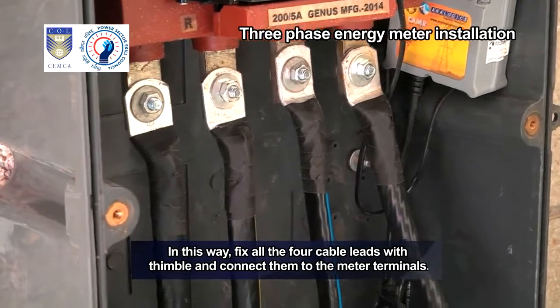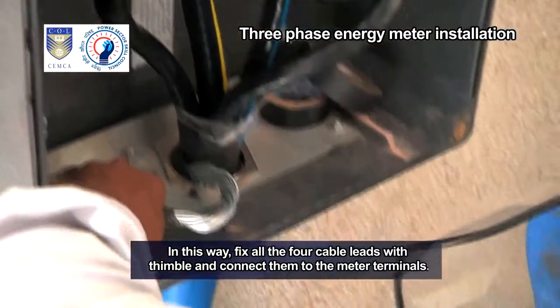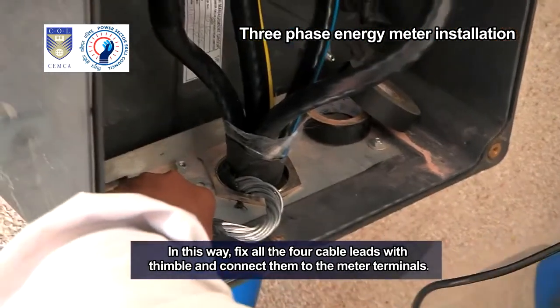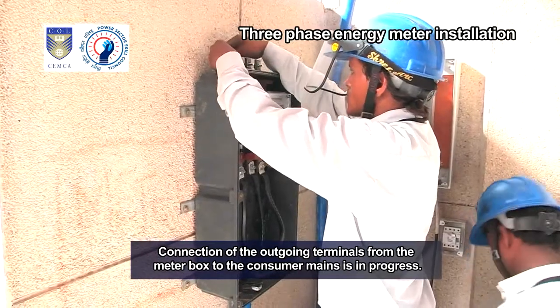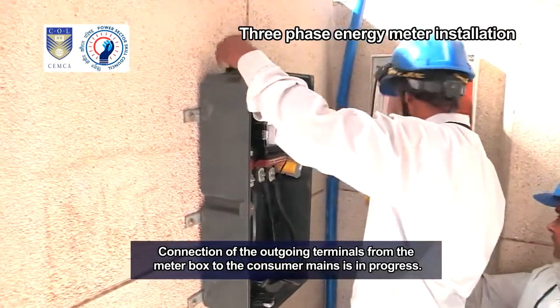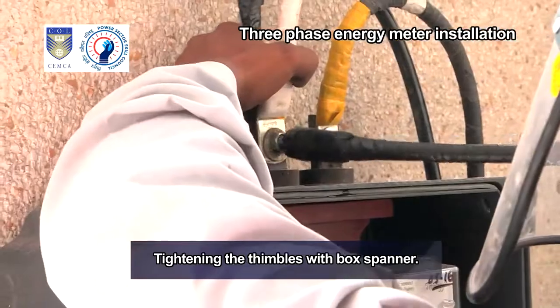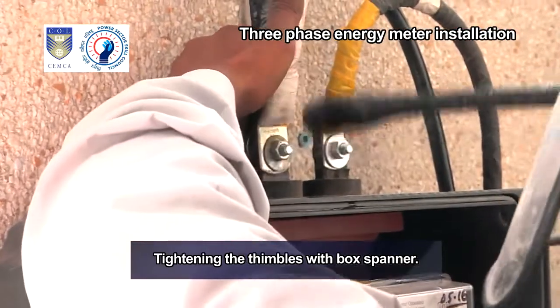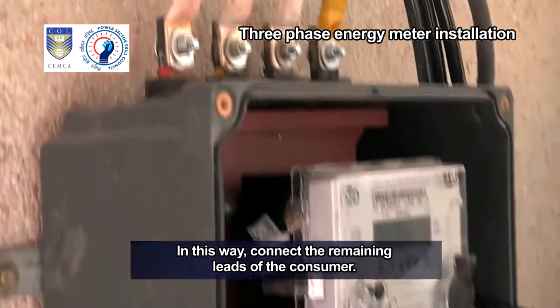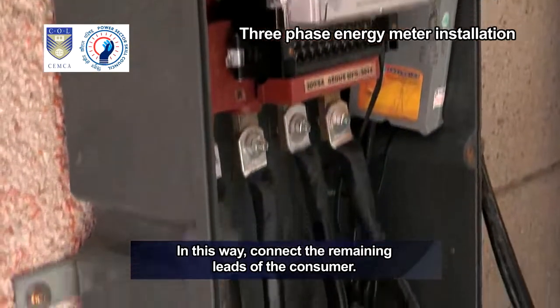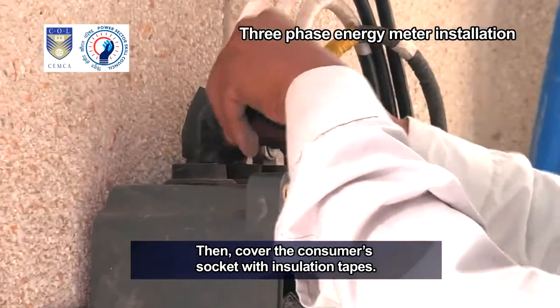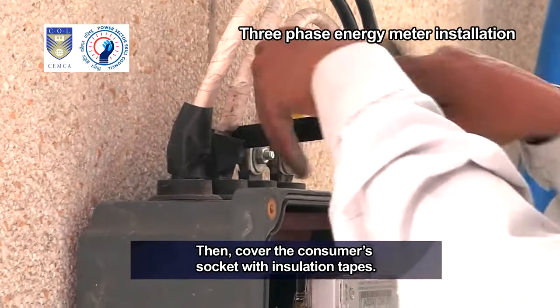In this way, fix all 4 cable leads with thimble and connect them to the meter terminals. Connection of the outgoing terminals from the meter box to the consumer mains is in progress. Tightening the thimbles with box spanner. In this way, connect the remaining leads of the consumer. Then, cover the consumer socket with insulation tapes.